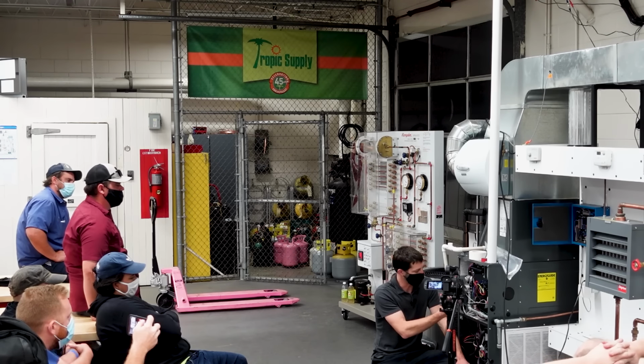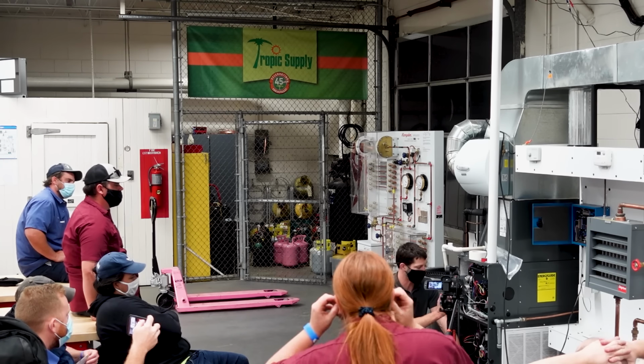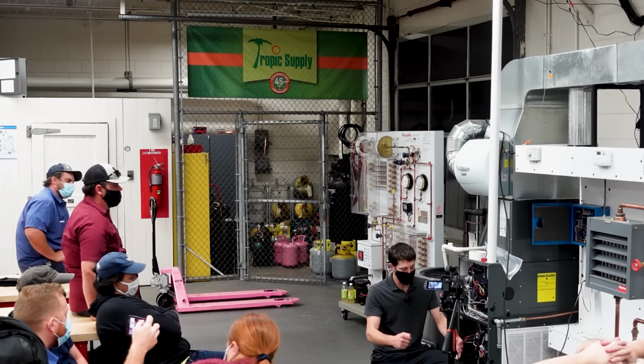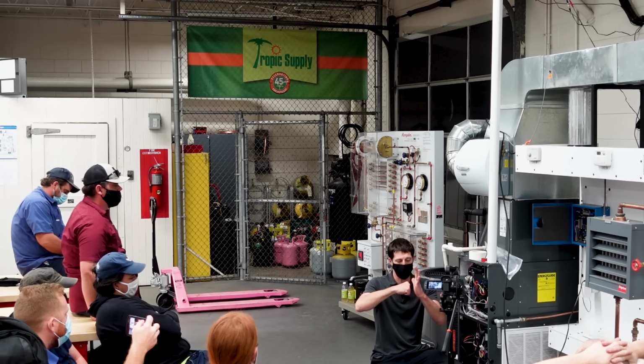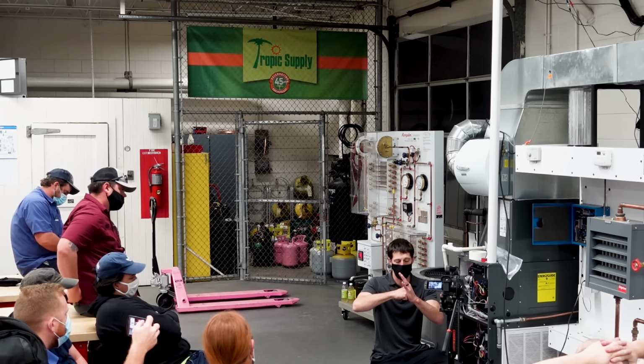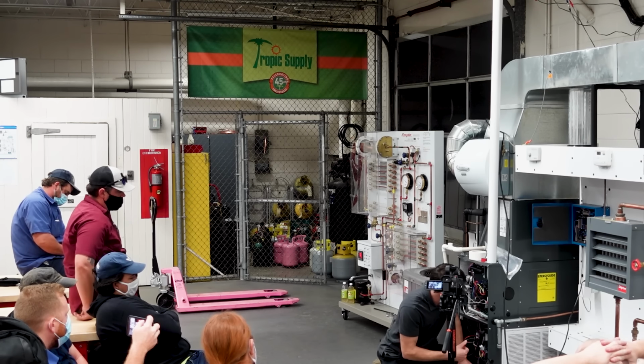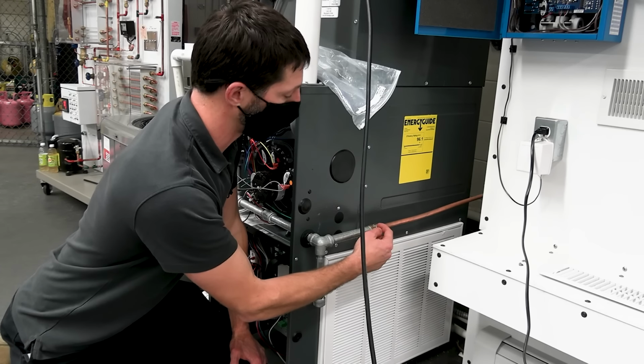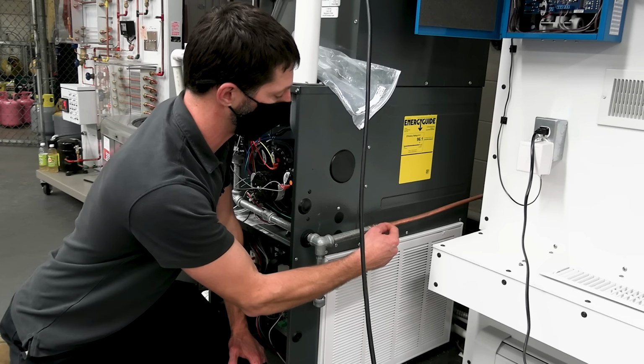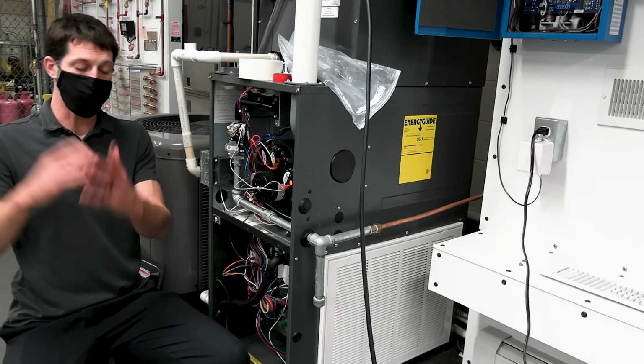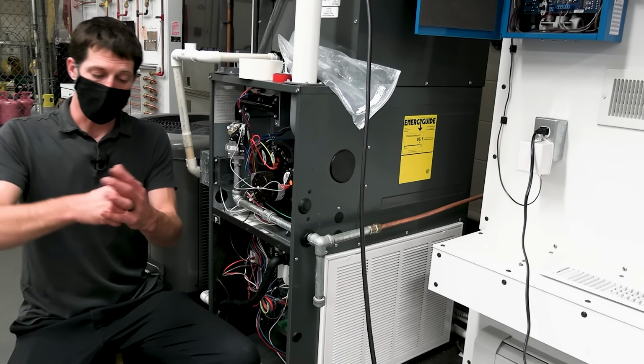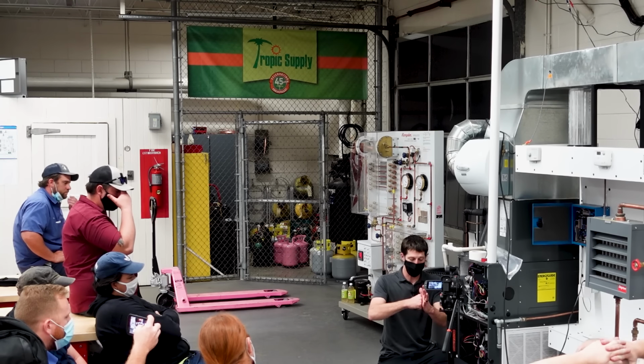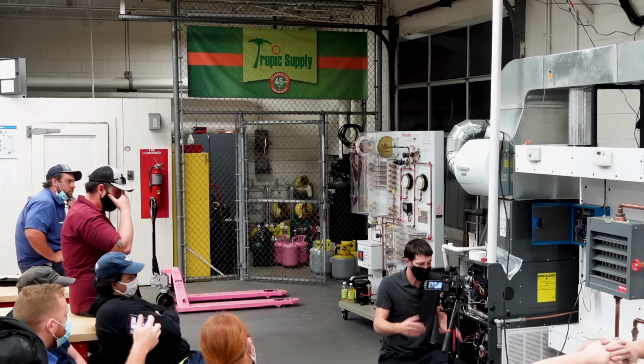This is not like a flare connection. These are threads that literally hold in the pressure, whereas a flare face is mated up against the flare adapter, and that's what seals in the pressure, not the threads on a flare adapter. Kind of like that one right there. You don't want to put any thread sealant on the flare face or on the flare threads, because that potentially could dry out over time, and then you have a possible leak point.